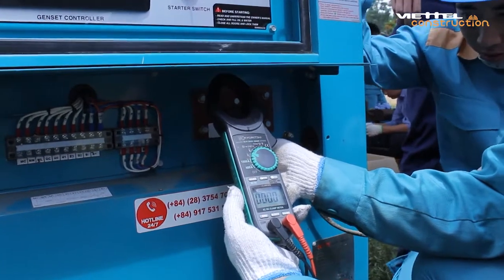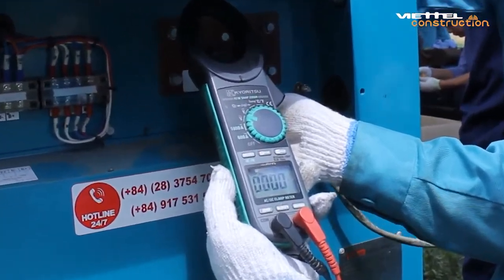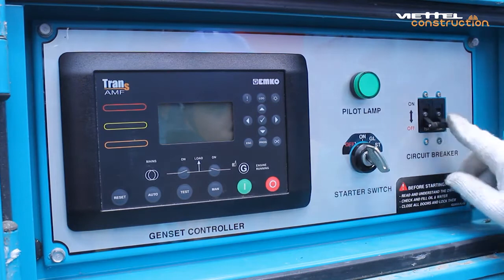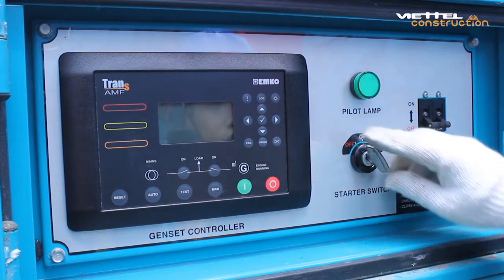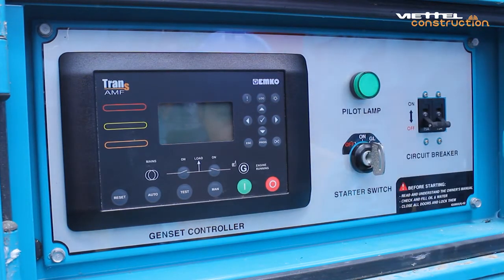Measure electrical leakage from the generator output station. Make sure the voltage is 0. After checking the guaranteed conditions, you start the generator and measure it in the no-load mode and in the loaded mode.